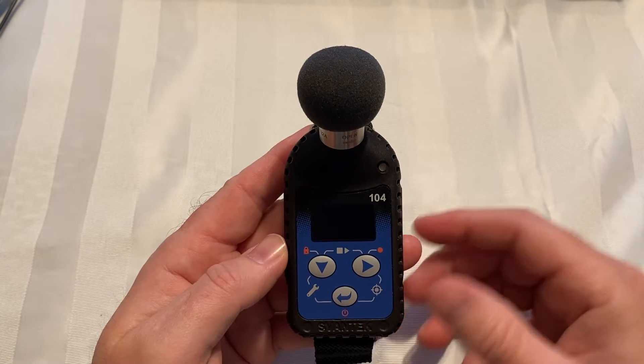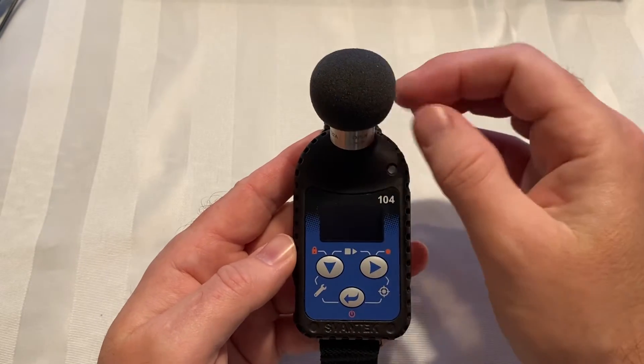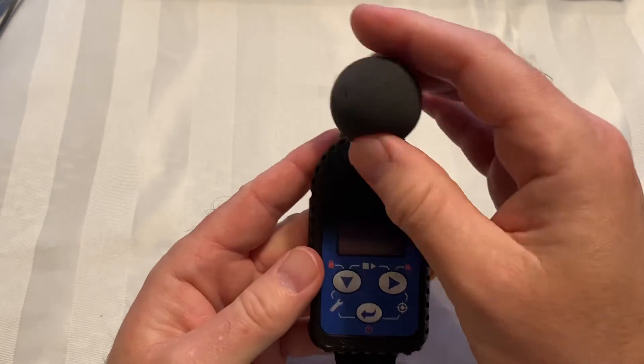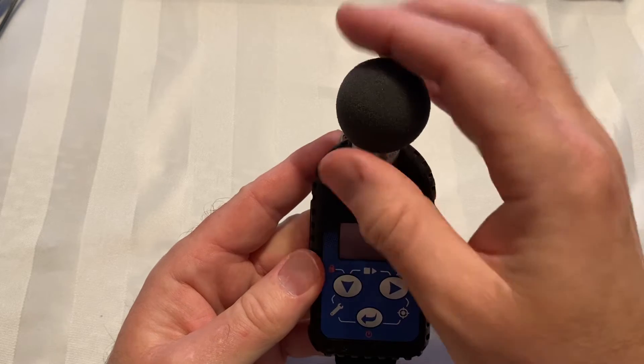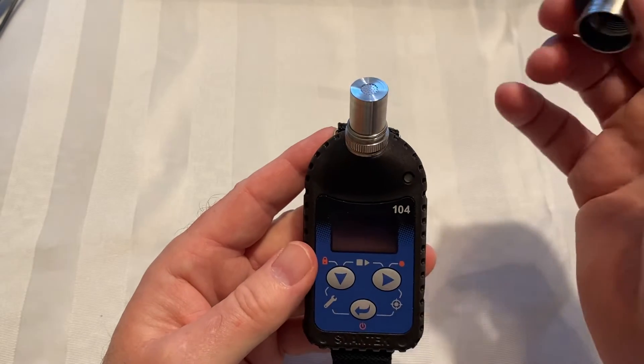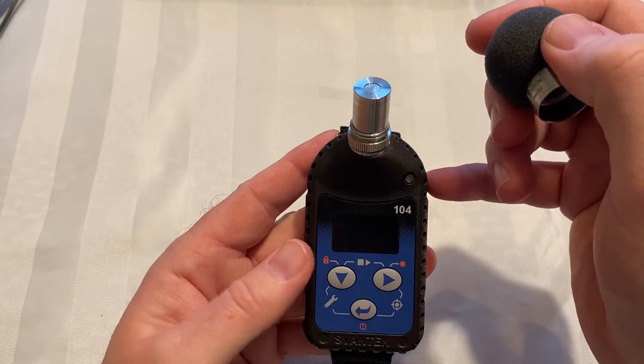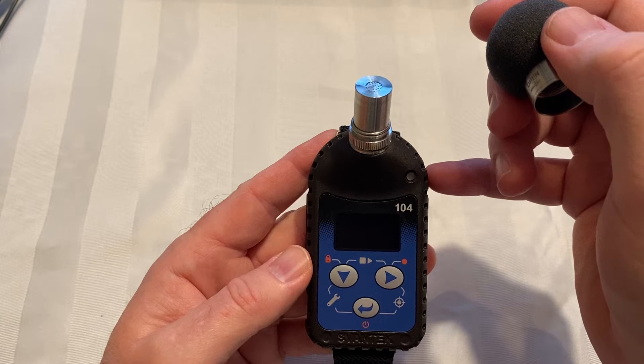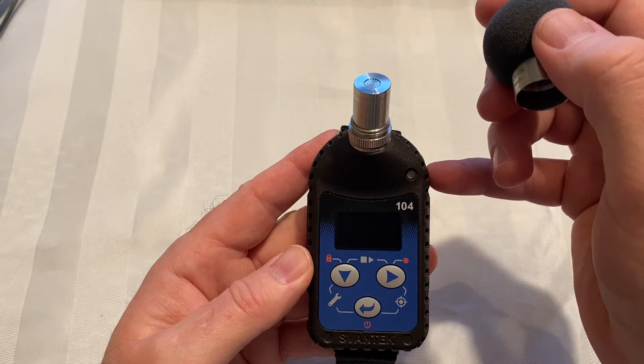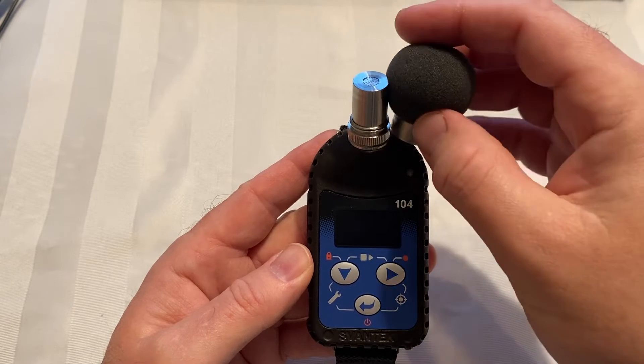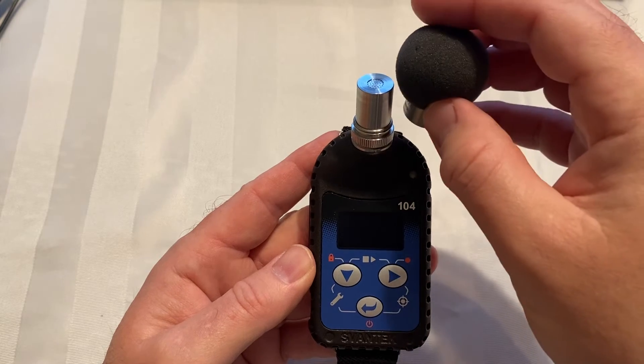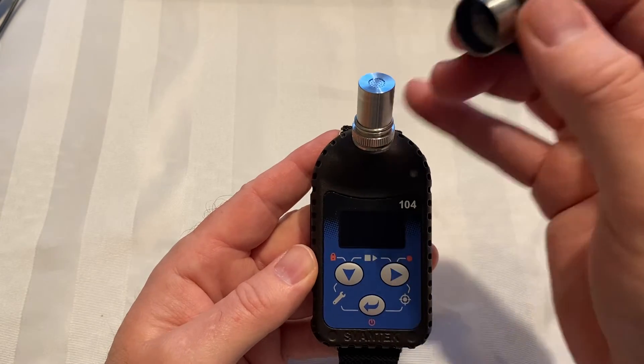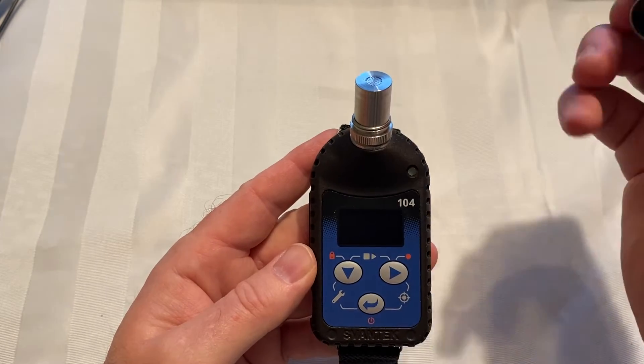First, I'll start with the windscreen. There's a little indication of how you take it off - this unscrews. Now there is an intrinsically safe version of the SV-104 called the SV-104BIS. It's intrinsically safe and has Bluetooth as well. With that version, the windscreen is magnetically held on so you just pull it off, but this one actually screws off the top.